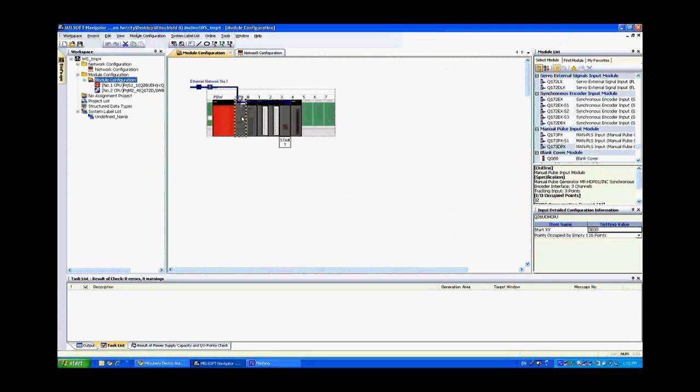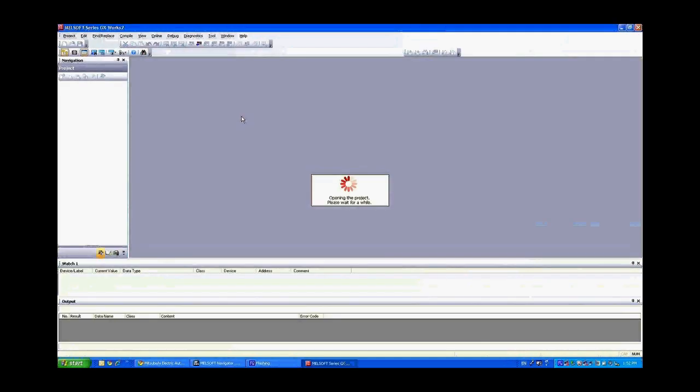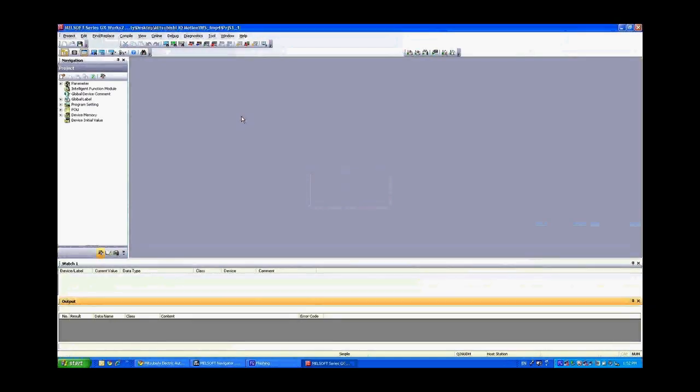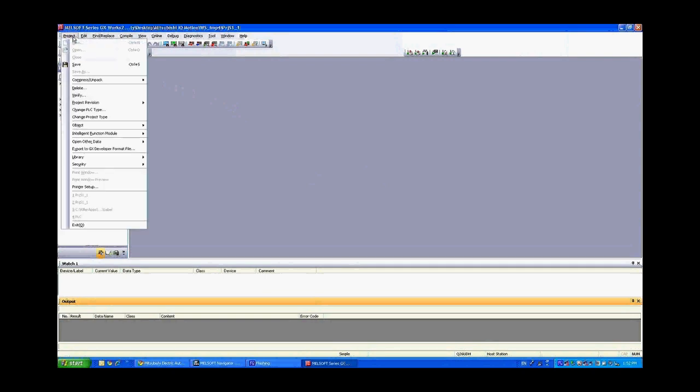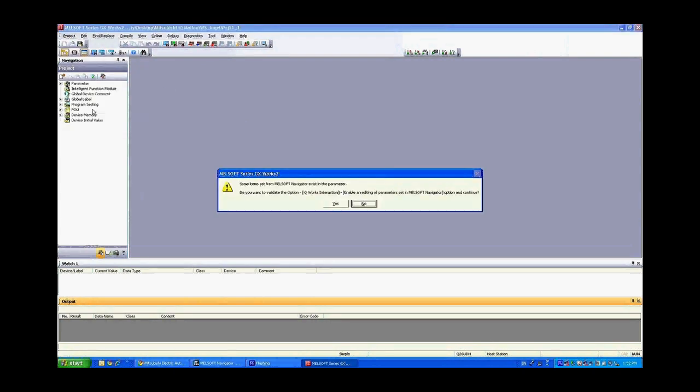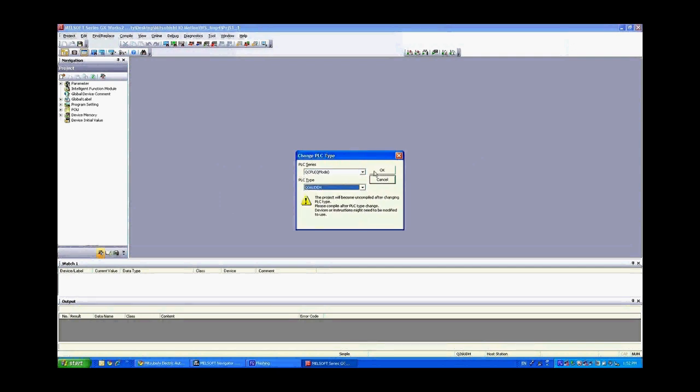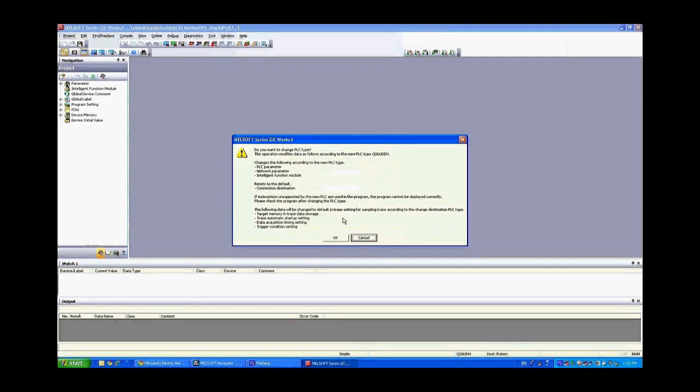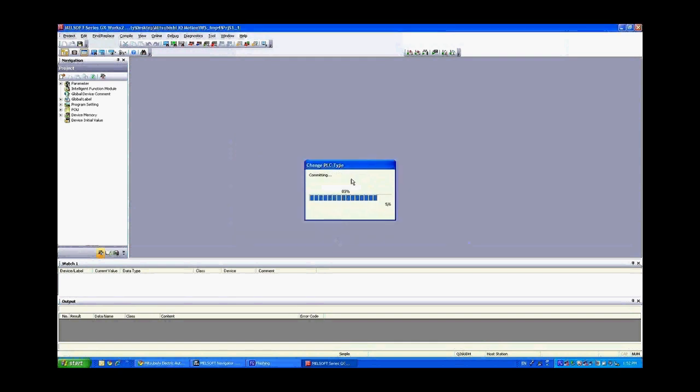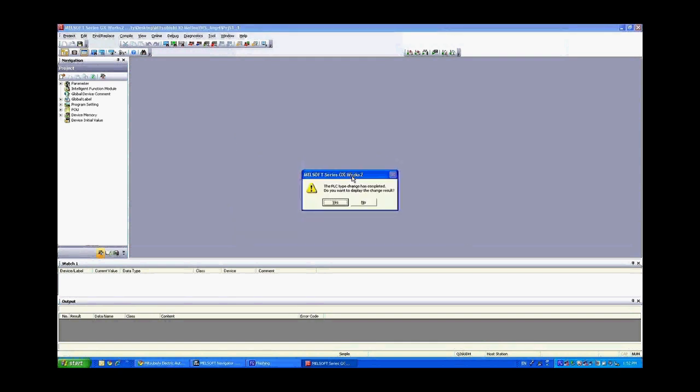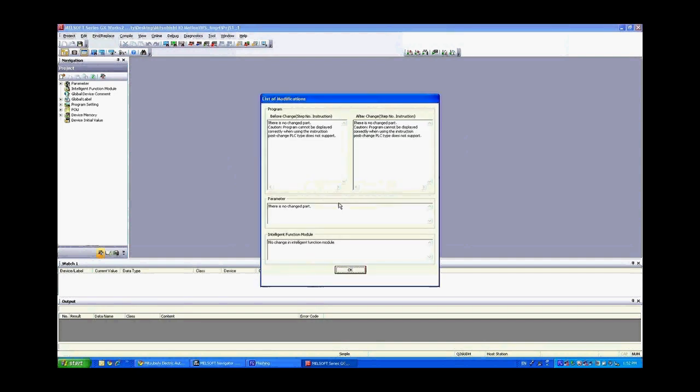So in order to change that let's double click on the PLC which will open up its project. Now from within the project we're going to want to change the PLC type. So go up to the project, change PLC type. It's going to tell us that right now we've set everything through MelSoft Navigator. Do we want the IQ Works software from the PLC side to send that information over to MelSoft Navigator. Click on yes. Here we'll select Q06UDH and say okay. It's going to ask us if we actually want to change it. Yes. And now it's completed. This will tell us exactly what has changed.